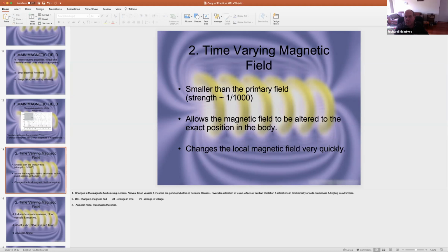So if we're just looking at one plane, we know that it's 3 Tesla in the middle, and at some stage it might be 2.99 Tesla, and it'll be 3.11 Tesla, or 3.01 Tesla at the other side. Okay, so it'll superimpose a magnetic field, and it'll change the magnetic field in that plane. And then it'll flip. So it'll go from 2.9 to 3.1, and this area will go from 3.1 to 2.9. And then it'll flip again. So if I'm a little atom here, next to the isocenter, I'll experience 2.9, 3.1, 2.9, 3.1, 2.9, 3.1 very, very quickly. So a small change in magnetic field, actually a lot less than 0.1, but a small change in magnetic field very, very quickly, okay?